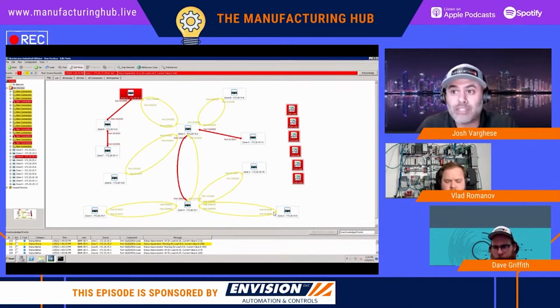context of industrial automation systems, certainly multicast messaging exists in multiple platforms. There's a version of it in GE PLC platforms. But in America, we know who's king as far as the control platform space. And so when Rockwell added the implicit messaging side to their platform, so not explicit, that is very clearly one-to-one messaging, they added implicit messaging, which has multiple names: publish, subscribe, produce, consume, implicit messaging. They've gone back and forth on this a lot, and they've made changes over the last several years.